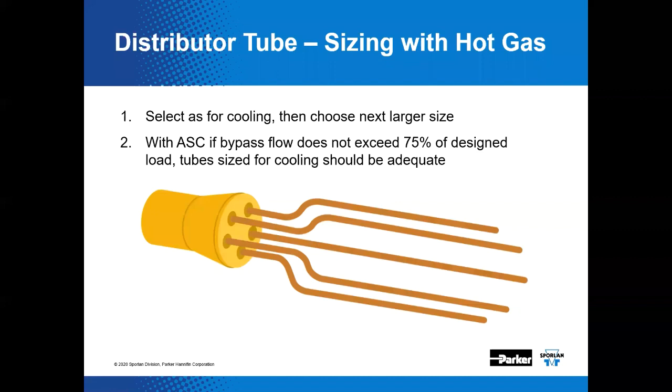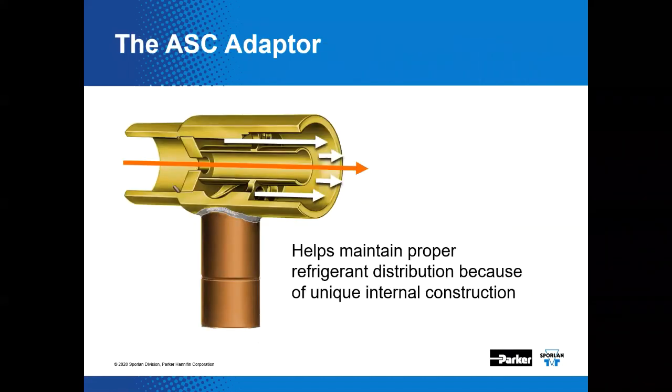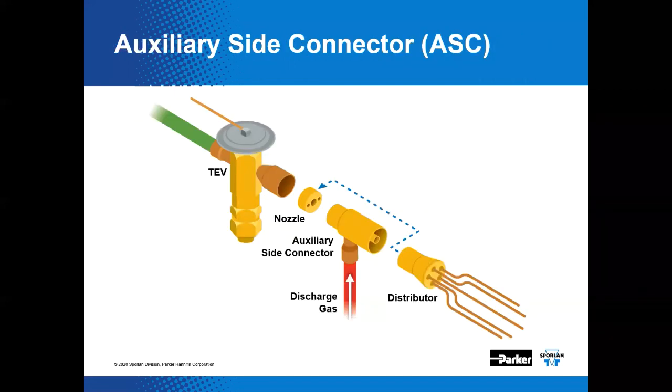Are there any questions coming in? Yes, we have a few. One asks: can unused circuits on the distributor be looped together instead of plugged if the correct distributor is not available? That's a very interesting question. It would seem that it would have essentially the same effect, but that's not something commonly seen done. Some field modifications observed include plugging only one outlet circuit — which is a bad idea — and drilling nozzle discs to make a larger orifice size, with varying degrees of success.